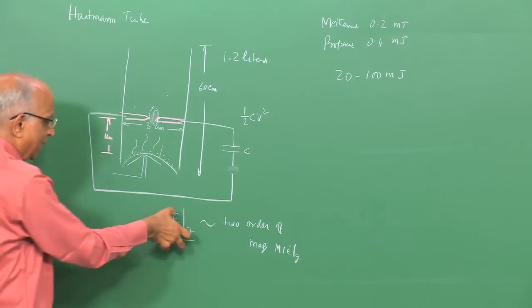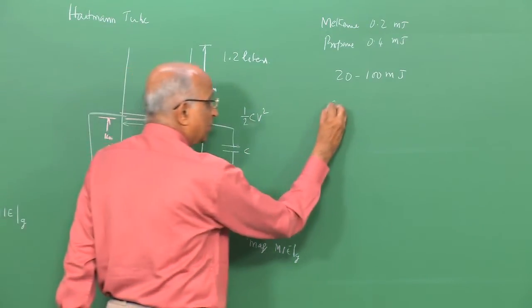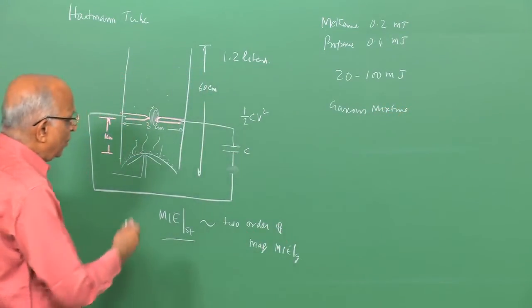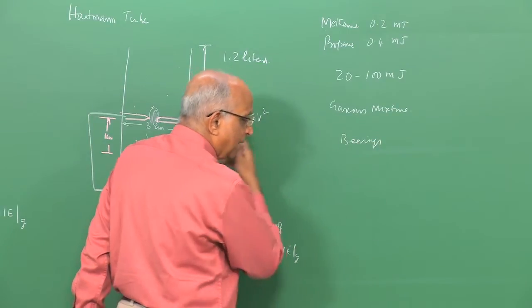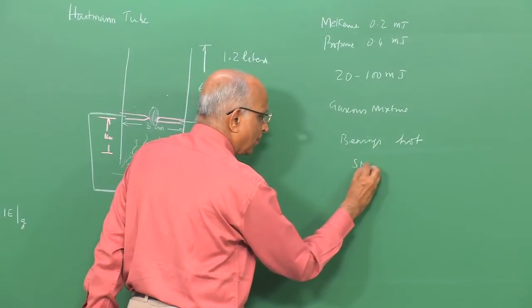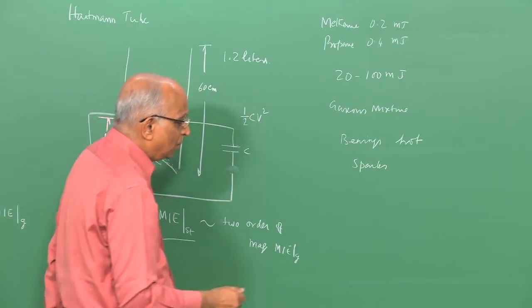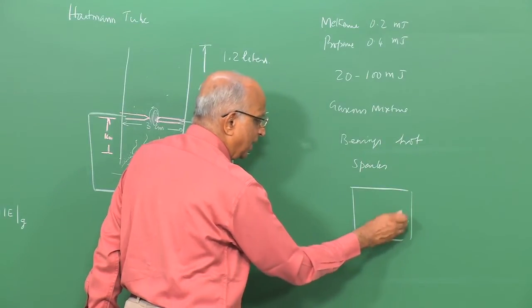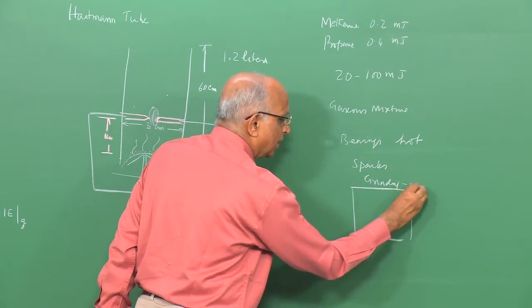Therefore, igniting a dust-air explosion is not going to be as easy as igniting a gaseous mixture. But we must realize that in practice we do get such energy release. If bearings supplying the dust get hot, I can have these ignition energies. Electrical sparks can deposit energy by arc discharge, typically a few hundred millijoules. In a dusty environment, if somebody is using a grinding wheel and sparks are flying, the sparks from the grinding wheel can as well initiate a dust explosion.